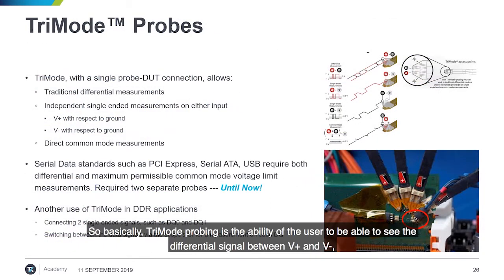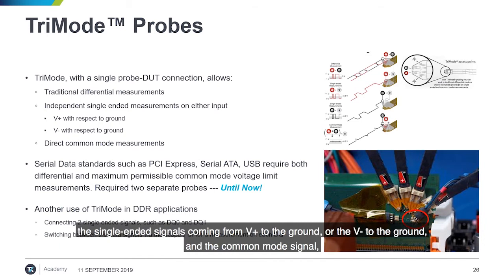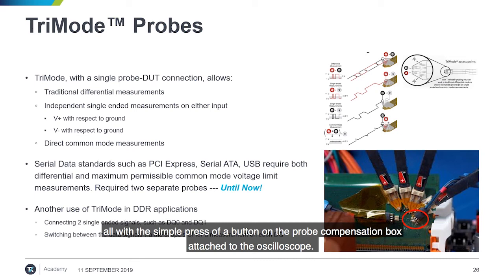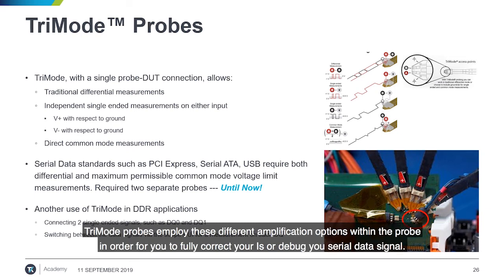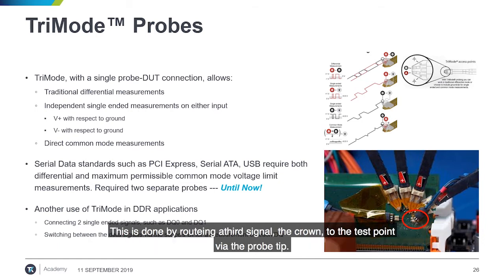So basically, tri-mode probing is the ability of the user to be able to see the differential signal between V+ and V-, the single-ended signals coming from V+ to the ground or V- to the ground, and the common mode signal, all with the simple press of a button on the probe compensation box attached to the oscilloscope. Tri-mode probes employ these different amplification options within the probe in order for you to fully characterize or debug your serial data signal. This is done by routing a third signal, the ground, to the test point via the probe tip.